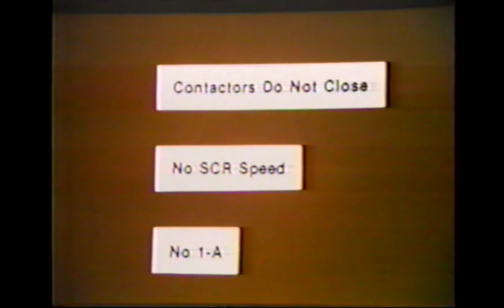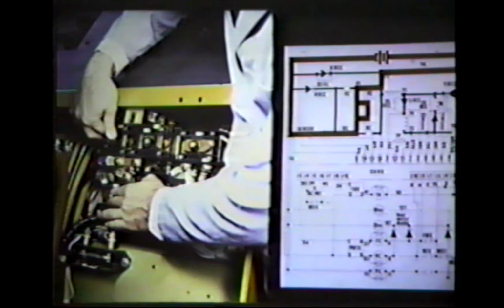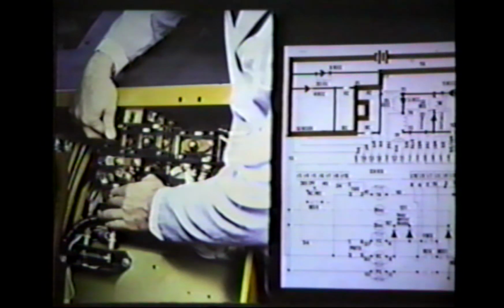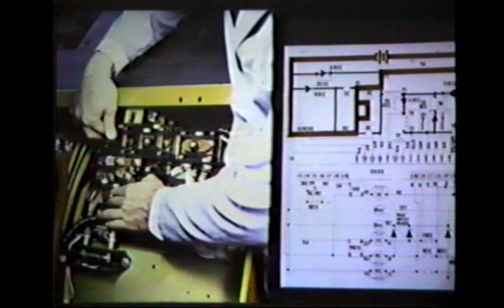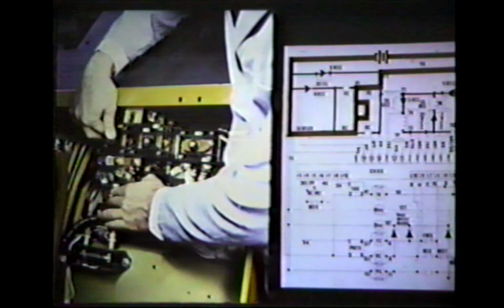The first symptom we will look at is also the most common problem on the EV-1 control because of the PMT function. The symptom is contactors do not close, so no SCR speed, no 1A. Manually close the 1A and either the forward or reverse contactor. The motor should now run. If not, check the circuit shown in red, which includes the battery and plug, main fuse, contactors, and the motor. If truck does run, continue to the next step.